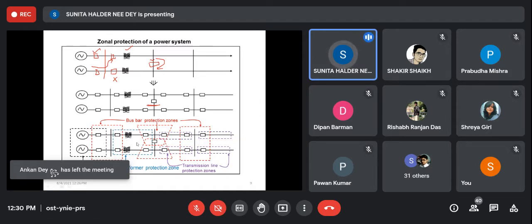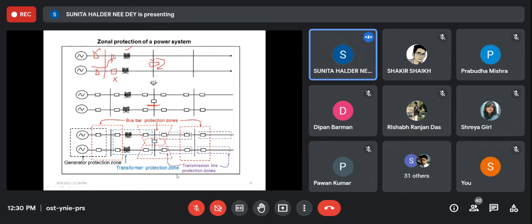These are called zones. So when we are providing protection on the generator side, it is the generator protection zone. Transformer side, transformer protection zone. Transmission line protection zone. When we discuss protection systems, generally we do not call it transmission line. In books, you may get feeder protection instead of transmission line. Transmission line and feeder are the same thing.